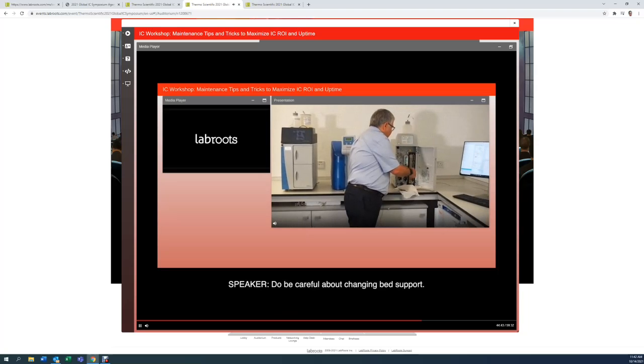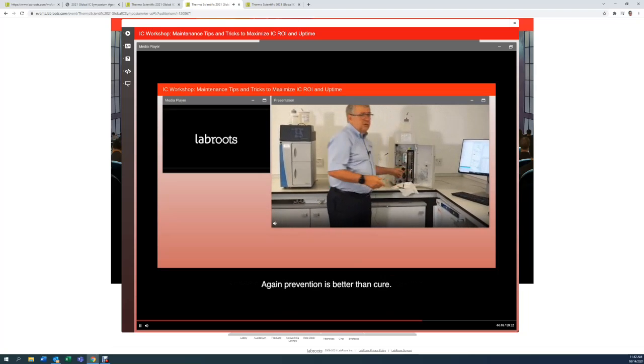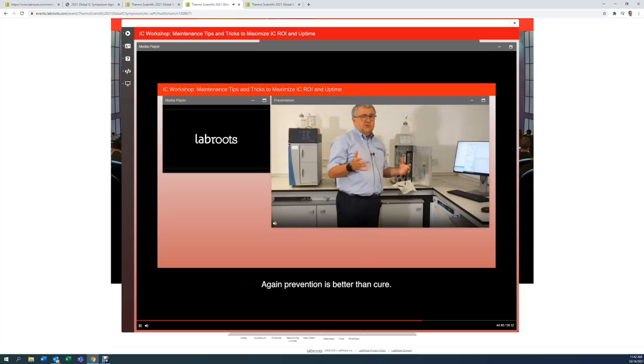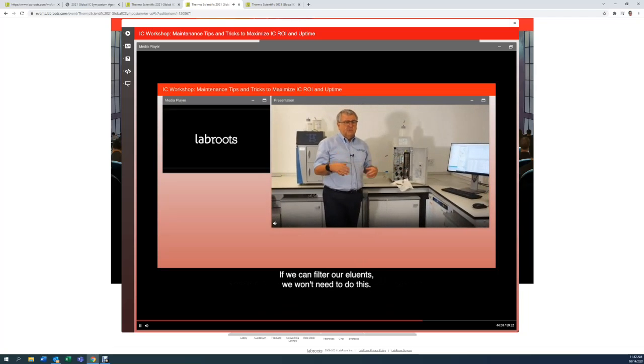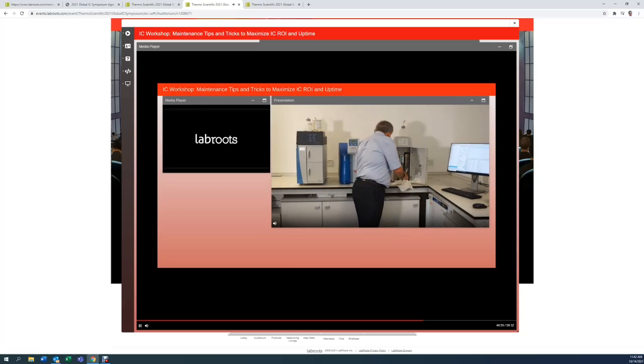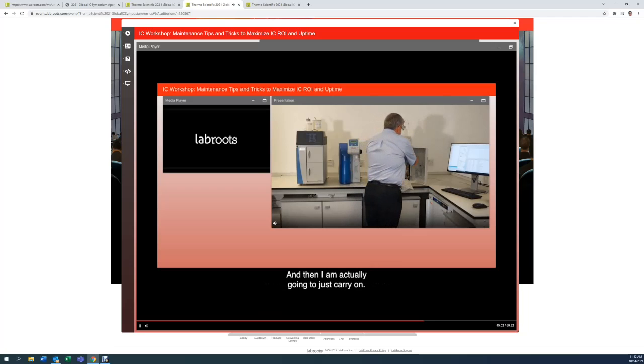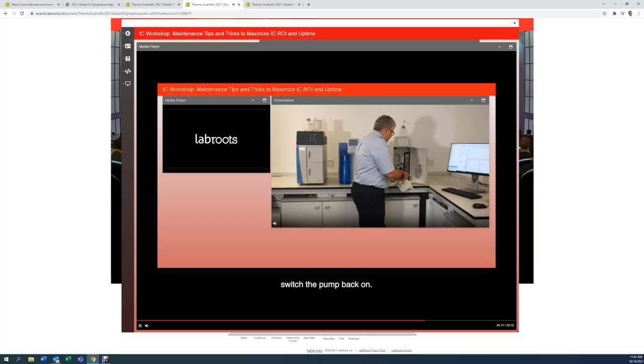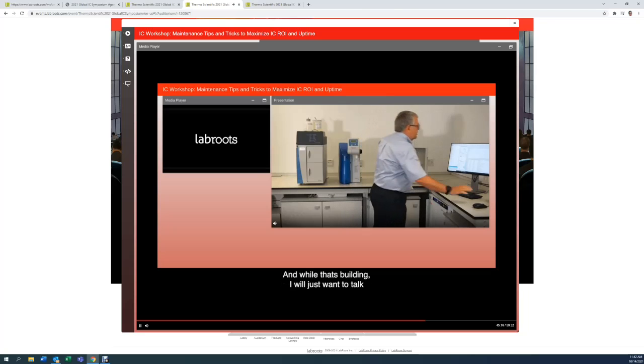Do be careful about changing bed supports. Again, prevention is better than cure. If we can filter our samples, if we can filter our eluents, we won't need to do this. I'm going to put the column back on, and then I am actually going to just carry on pressure checking the instrument, just for completeness, just to make sure there isn't anything else happening. I'll switch the pump back on.